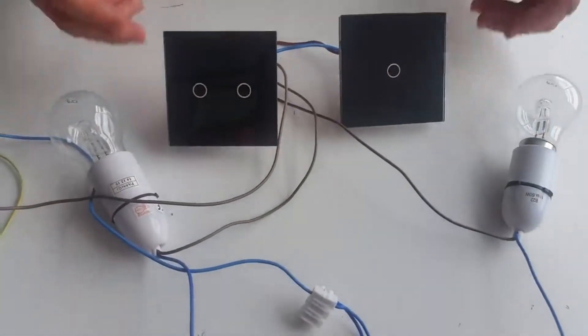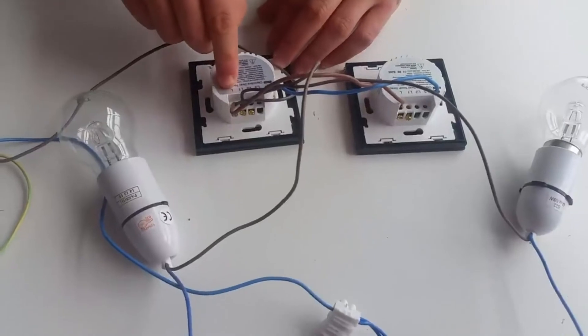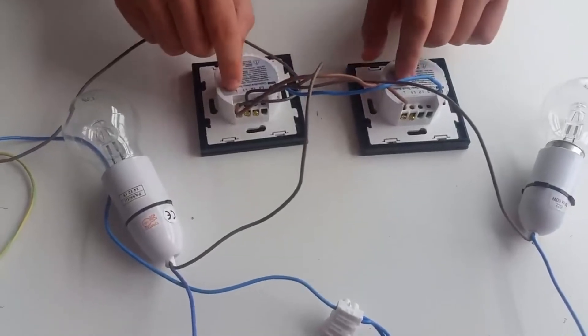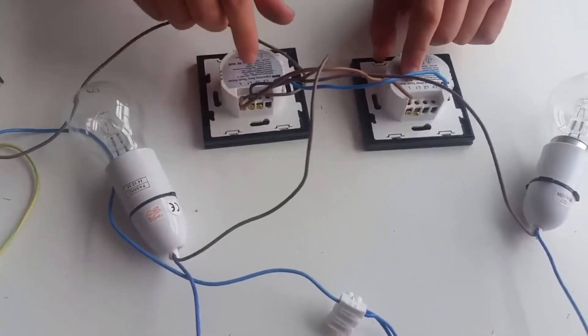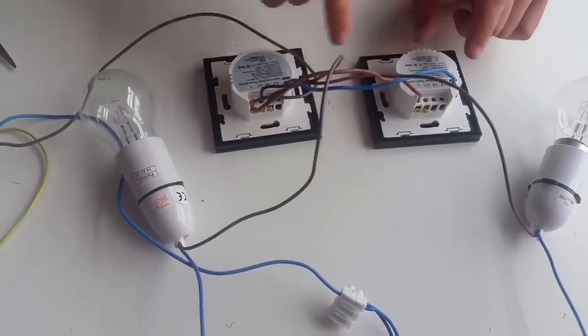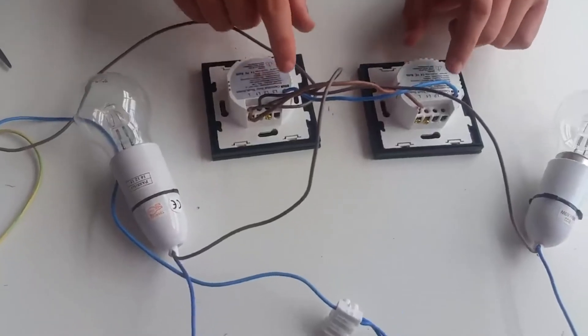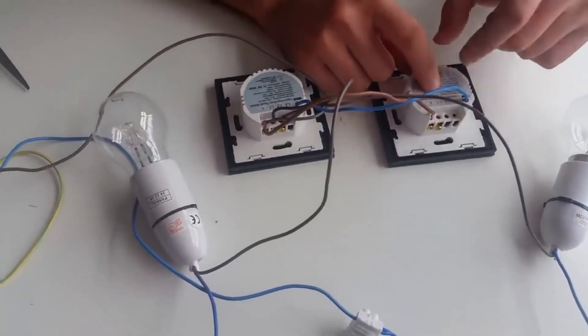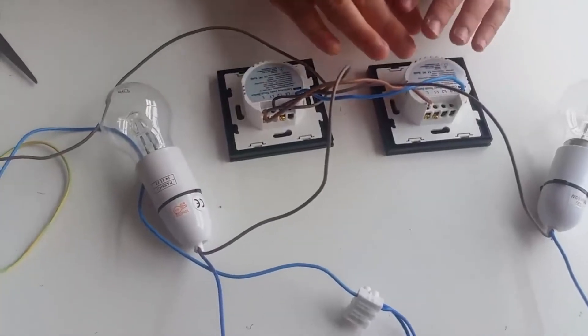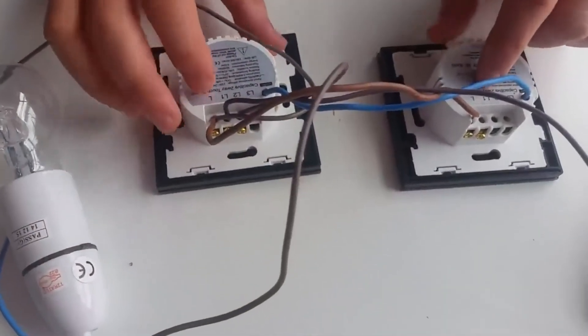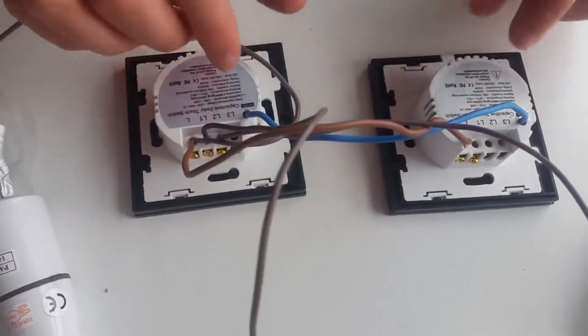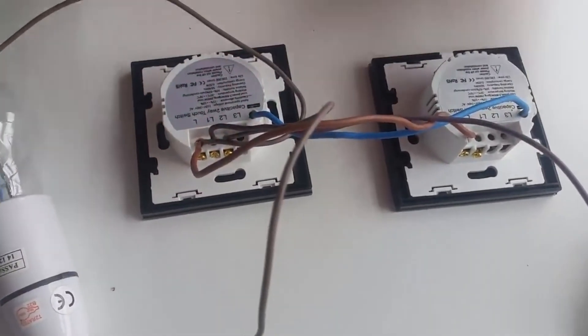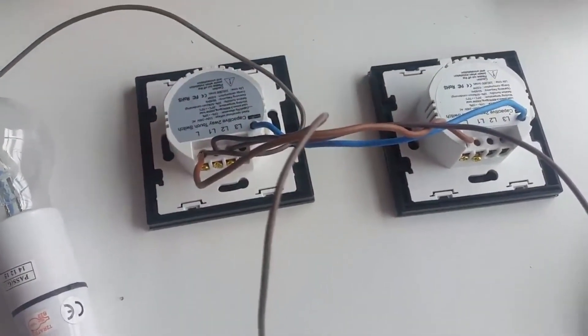So basically L is your main cable along with the cable to the other switch which gives it power. L1 and L2 will be your main switch cables and the two-way to make it work as a two-way. As you can see, the L1 terminal on the second switch is left empty and it does not require any other cable to be connected from this L1 to this L1, as the two-way terminals is what does the job. Basically that is it and thank you for watching.